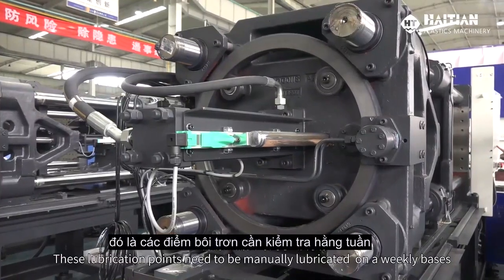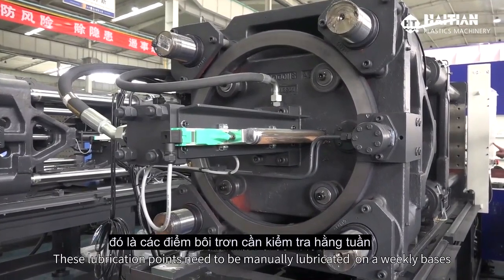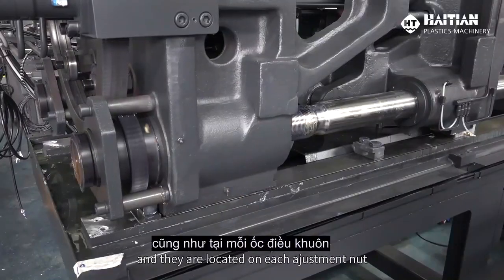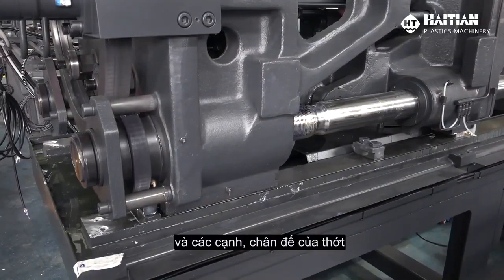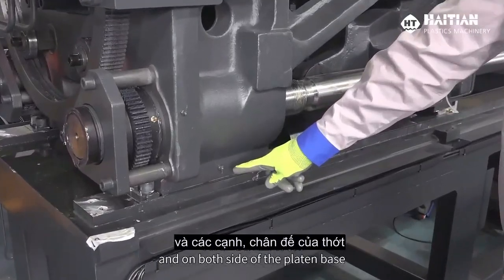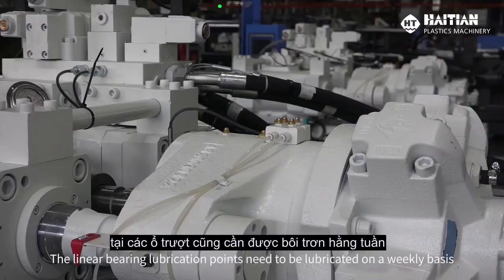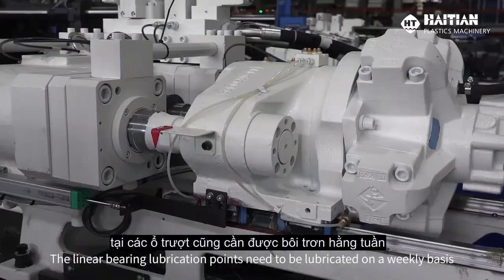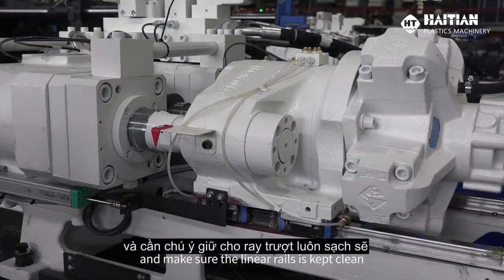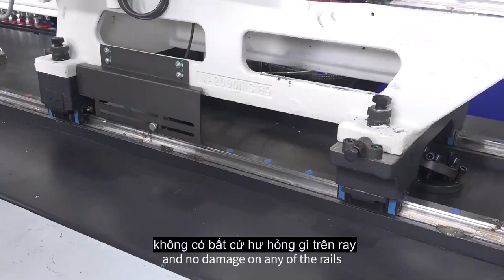These lubrication points need to be manually lubricated on a weekly basis, and they are located on each of the adjustment nuts and on both sides of the platen base. The linear bearing lubrication points need to be lubricated on a weekly basis and make sure that the linear rails are kept clean and no damage on any of the rails.